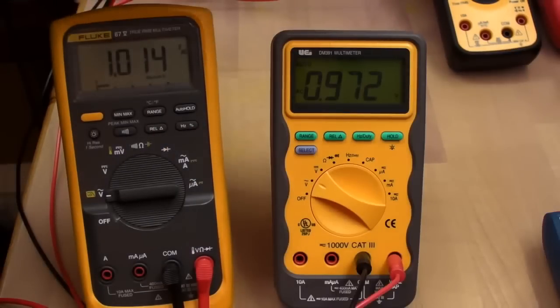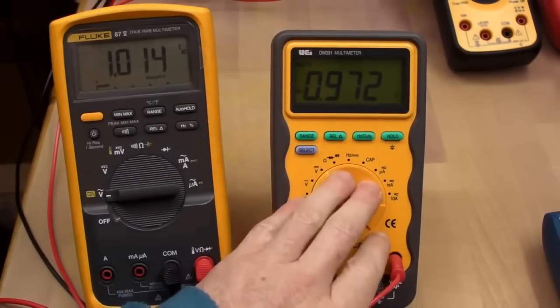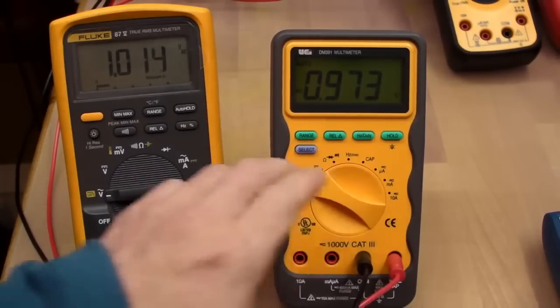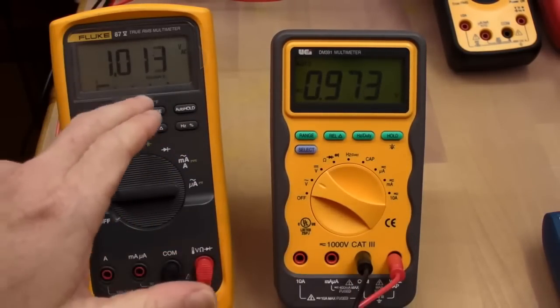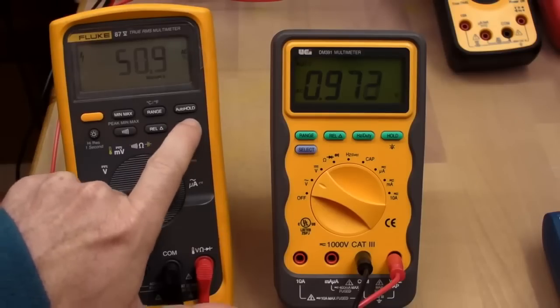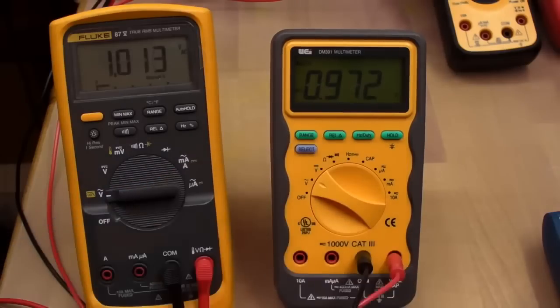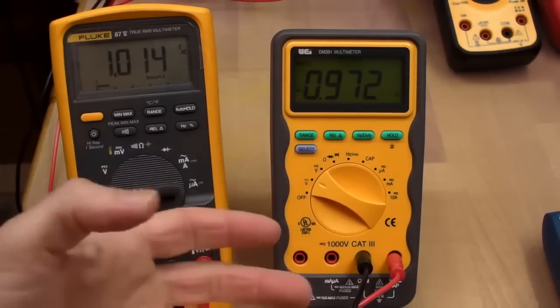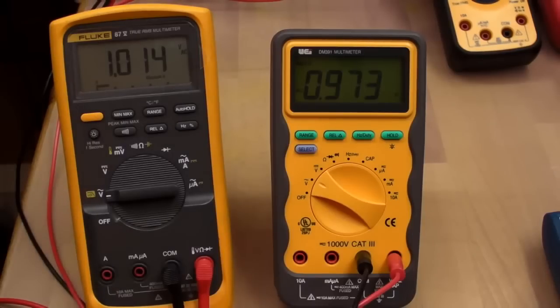The same thing with the UEi, but the only issue with the UEi is this is not true RMS. As you can see, I've got it back down to 300 hertz, and really the UEi doesn't match the Fluke because it's not true RMS. Whereas if we put it to a sine wave, there we go, it's a sine wave now, and as you can see, it's spot on. But when you do it to a square wave, or that's the triangle wave, as you can see, it's out because it's not true RMS.